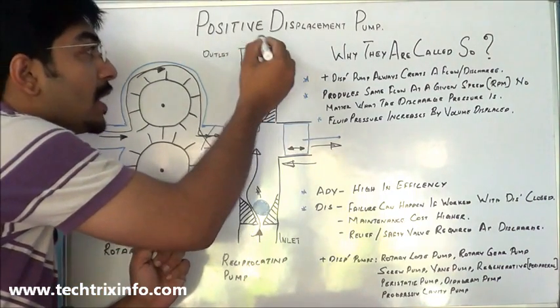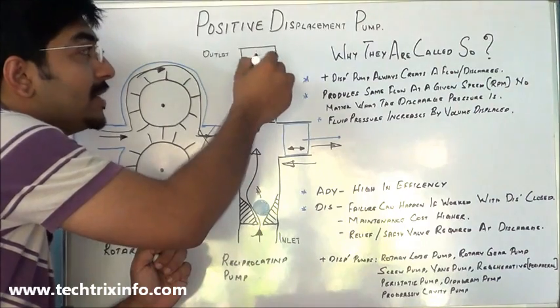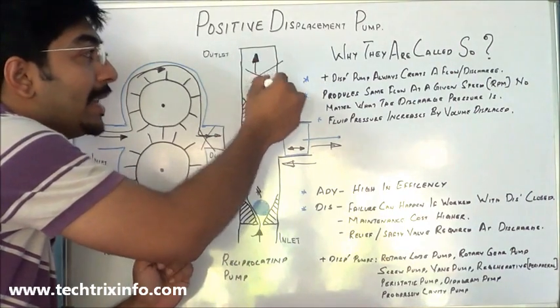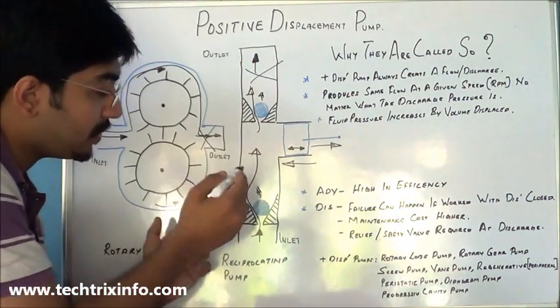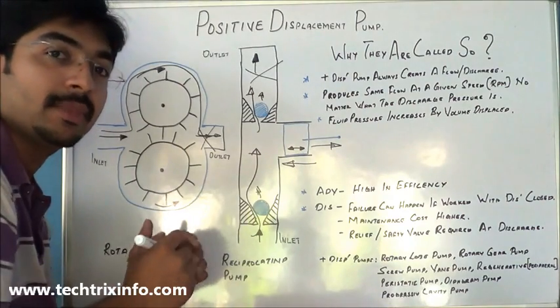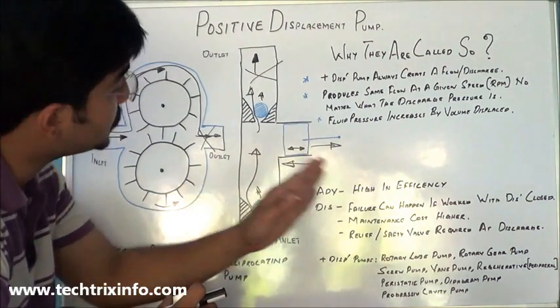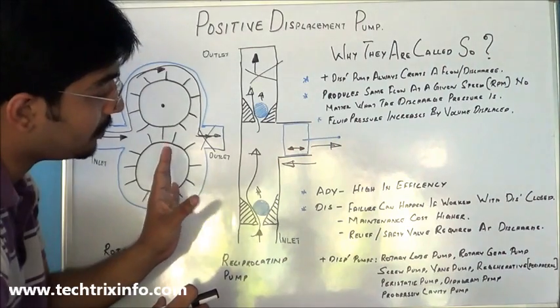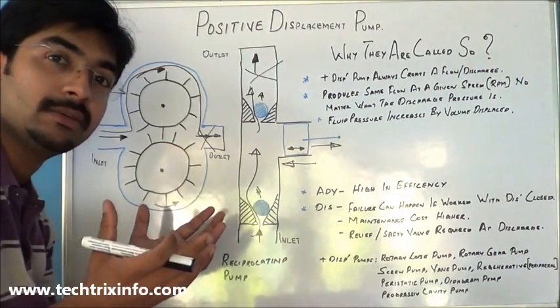Whenever this reciprocating pump works, there will always be a displacement. So if we close the outlet, pressure will develop in that region and result in the mechanical failure of the reciprocating type pump.